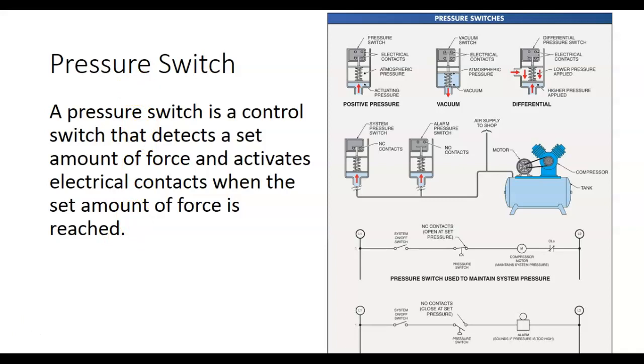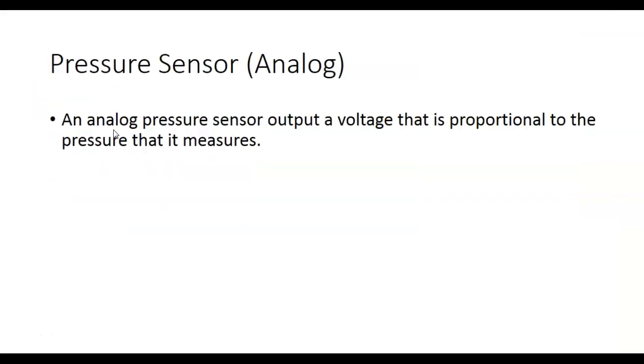RTDs, those do it without any electronics. But we have to add something because we can't transmit resistance - we can transmit current and voltage. Those are the two things most sensors use: either voltage or current. Most analog sensors run from 0 to 10 volts or 0 to 5 volts. Digital sensors are usually 0 and 24 volts. That's most of what we do.